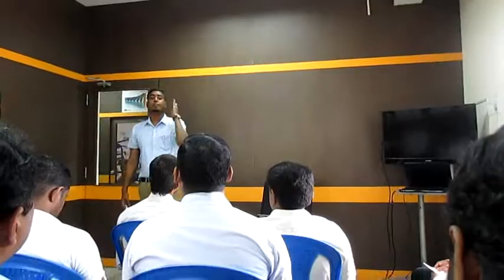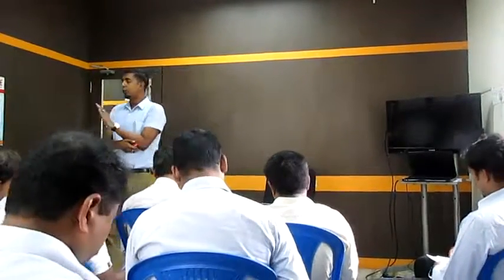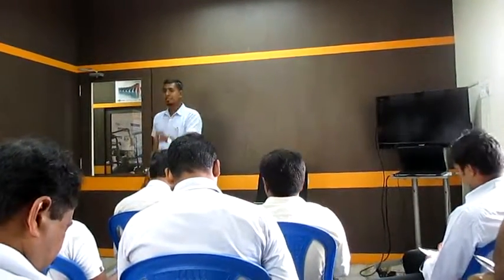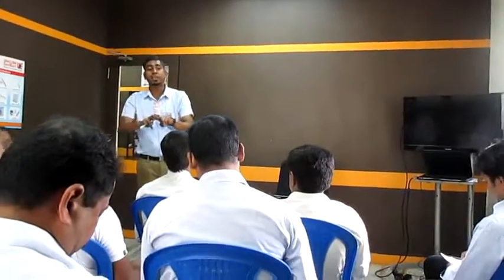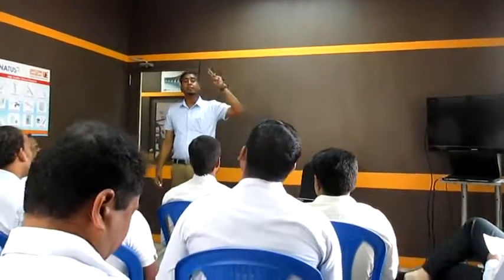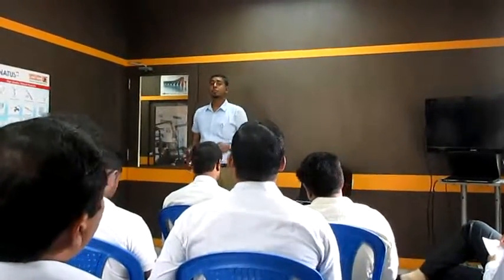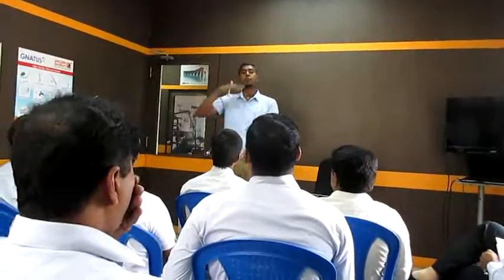As per AERB guidelines, after every 2 years you have to do a QA. So why do we need a QA? And why is AERB there? AERB doesn't want you to be at radiation risk. AERB doesn't want a patient to be at radiation risk. The QA should be done for every machine, either dental or medical, after every 2 years, because AERB believes that after every 2 years of use, the parameters will change.